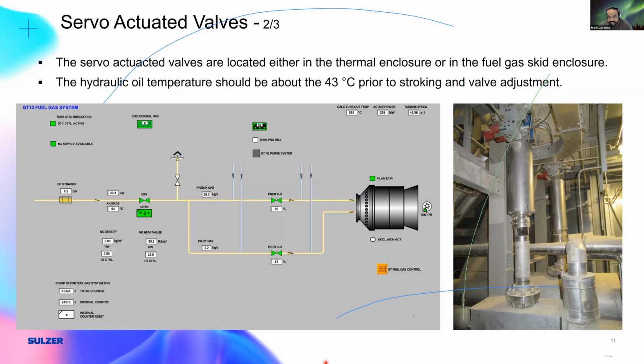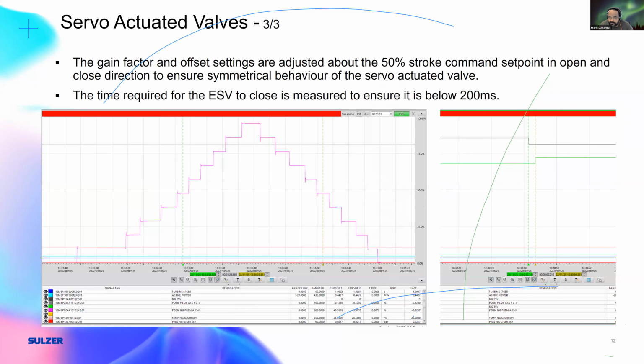After I come to site and these valves are overhauled, sometimes they're taken out for service to a different company, and when they are brought back, I have to make sure that they function the way they did before. In order to do that, I position the valve at a 50% stroke, and then I go from open to close and from close to open. And in doing so, I try to determine the offset that allows me to have a value that's symmetrical around the 50% stroke command. Once I'm successful with that, I change the gain factor of the valve.